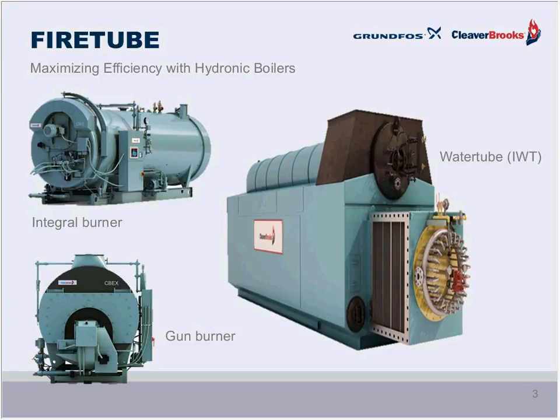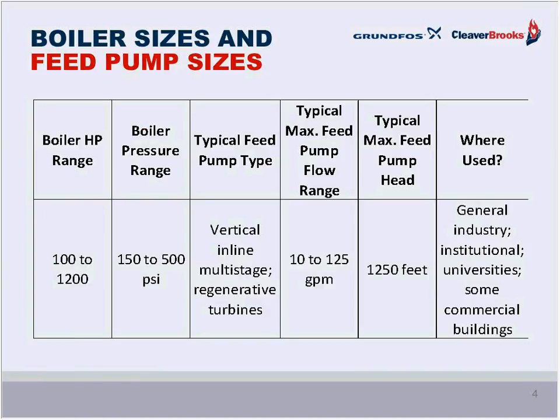All right, as I mentioned, I just wanted to reflect back to last month in Part 1 when we discussed some boiler feed equipment basics and pump sizing criteria and the selection. And said at that time that we would be concentrating on these types of boilers as they are the most commonly used when referring to boilers spanning a size range of between 100 and 1,200 horsepower. And, of course, design pressures, as I mentioned before, 150 to 500-pound design. Again, it's the fire tube and industrial water tube boilers which are most commonly specified and applied in these areas of operation.